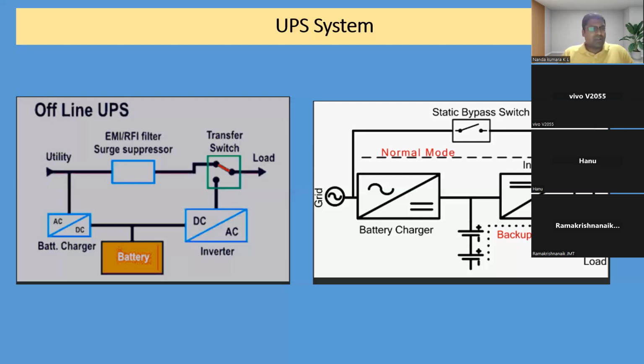If you see, the first one is offline UPS, where the utility source is there, that is grid power, then EMI or RFI filters, that is the surge protector, then the ATS, auto transfer switch, then the load. The same parallel line is connected to the rectifier, then battery, then inverter, and to the auto transfer switch, it goes to the load. In this scenario, only in case of power failure, this auto changeover switch will switch off from grid power, utility power, and connect to the inverter side, so there will be a drop in the load, then it reconnects. That is called offline UPS.